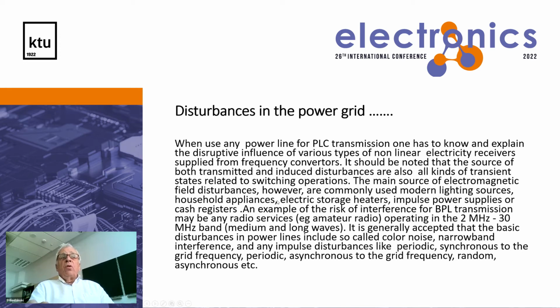Household appliances, which also use electronic devices, electric storage heaters, and first of all, impulse power supplies - nowadays we use impulse power supplies. Another factor is the change of load being varied from inductive load to capacitive load, therefore compensation is already a problem, and we have to use special active filters to handle that. Otherwise, we won't be able to do it. This is a general threat from using modern techniques nowadays.